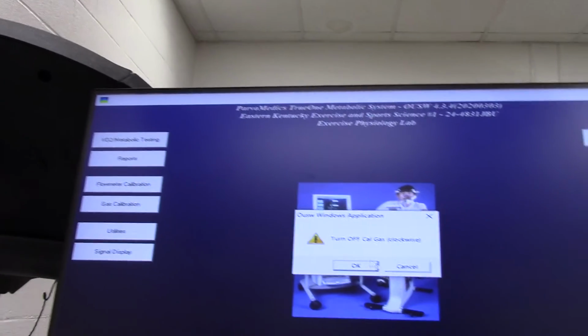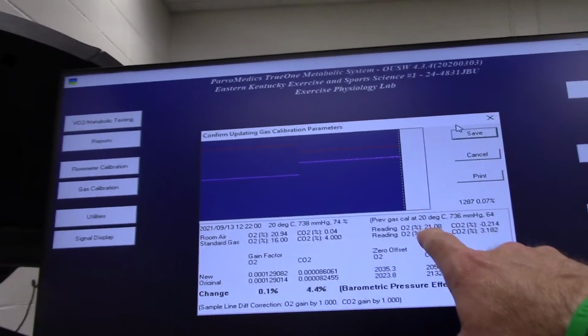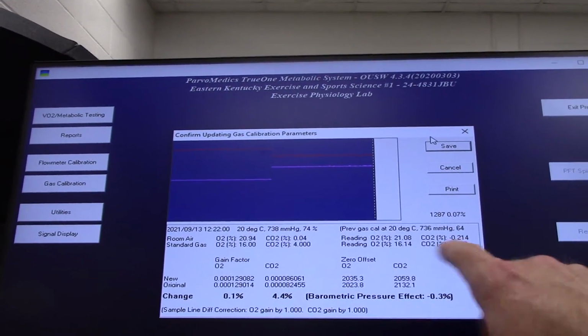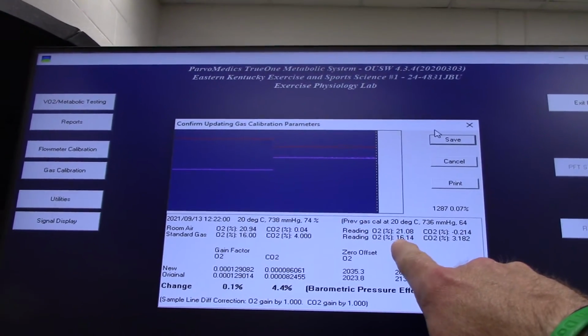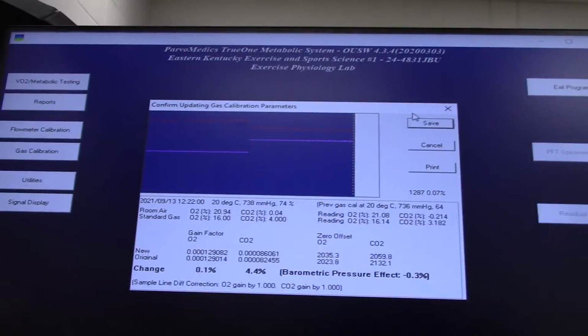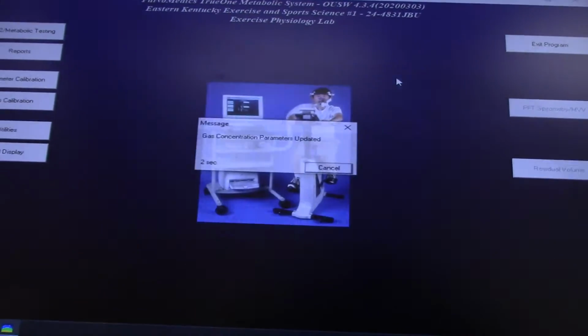Go ahead. We're going to close that off, so we're going to turn it back. Good. Just snugging it. We're not trying to break it. That's perfect. And we hit OK. Our numbers should look realistic. So ambient air, you see, is pretty close. Then this should be 16.0 and this should be 4.0. That's where it's going to make the modifications to our baseline for calibration, and we're good to go. And so from there, you can go ahead and do your metabolic testing.